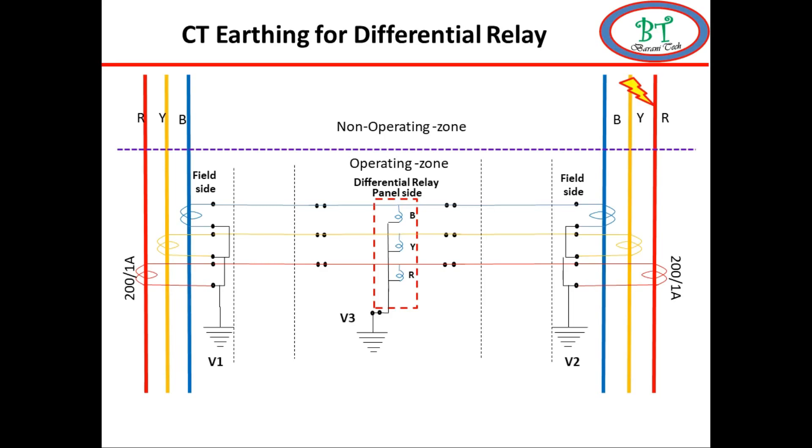During this fault the unbalance current is produced, which lead to neutral current flow. And this make a potential difference on each earth point. This potential difference will make an additional separate current on neutral path. Which lead to differential trip.